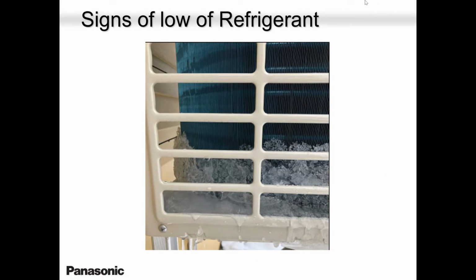This picture, I got it from a contractor. It was low on refrigerant. So it was not very low, but it was low enough not to completely defrost the coil. And that coil at the bottom there, as you can see, it's fully frozen. That is dangerous. Dangerous, as you know, it can cause the coil to burst.